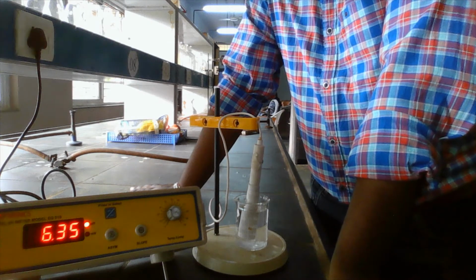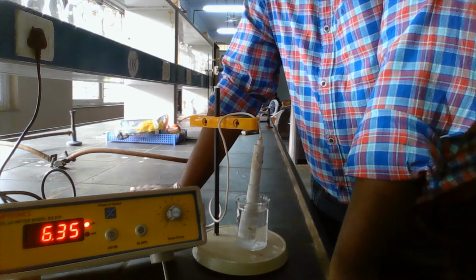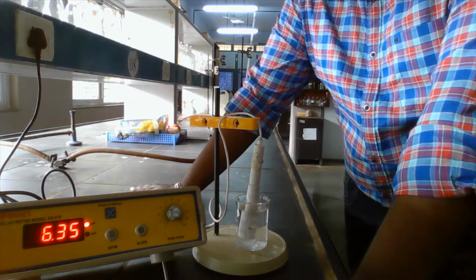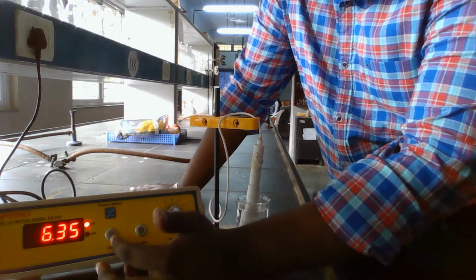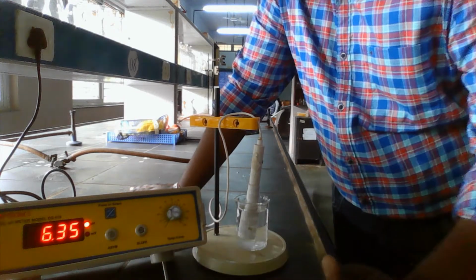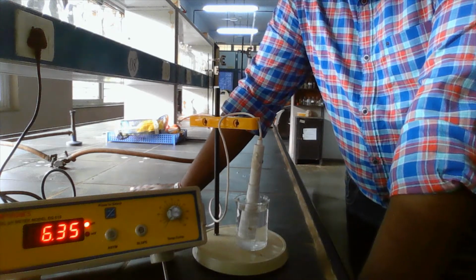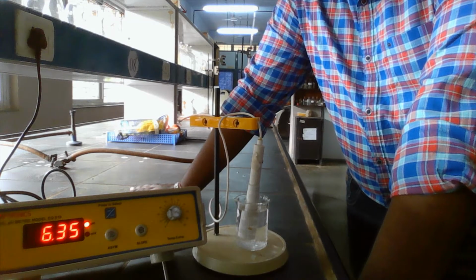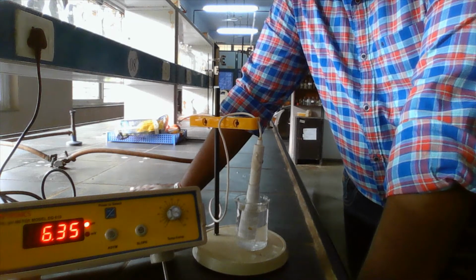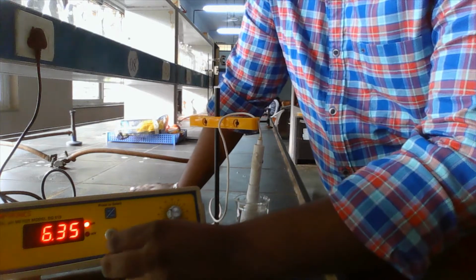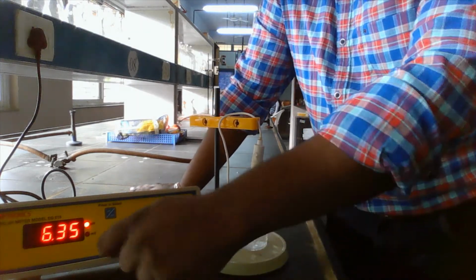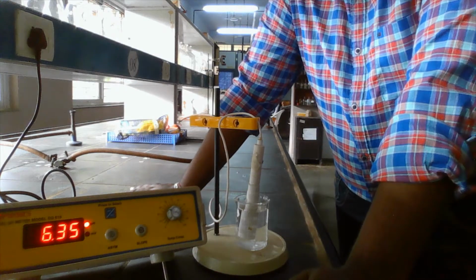I have taken the tap water, and the tap water pH you are going to get is 6.35, the actual reading. But what is the use of this calibration knob? Before starting the instrument I have calibrated it, meaning standard pH solutions of known pH 4, 7, 9 are with me, and I have kept them. If any adjustment is needed, there is a small pen-like structure, with the help of which we have to adjust, and then I have taken this reading.